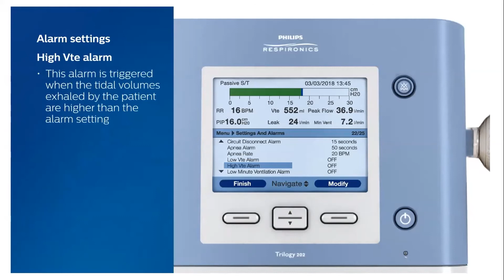Minute ventilation is respiratory rate times tidal volume. The low and high alarms can be set between 0.2 liters per minute and 99 liters per minute and should be set according to the patient's breath rate and tidal volume.